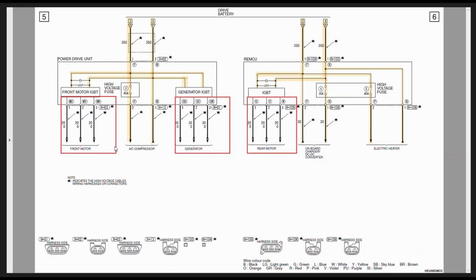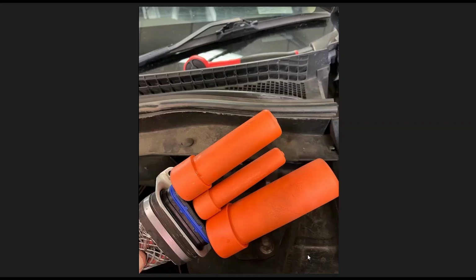certification, etc, etc. I did come across these, which I thought were quite cool, when you are disconnecting high voltage cables from inverters, etc, these protective tubes. I chose to show all three there because we've got three different diameters. Just nice to keep protection over the terminals, so that we don't get dust or debris or contamination, which ultimately increases resistance. And we're always looking at milliohm resistance when we look at high voltage connections.